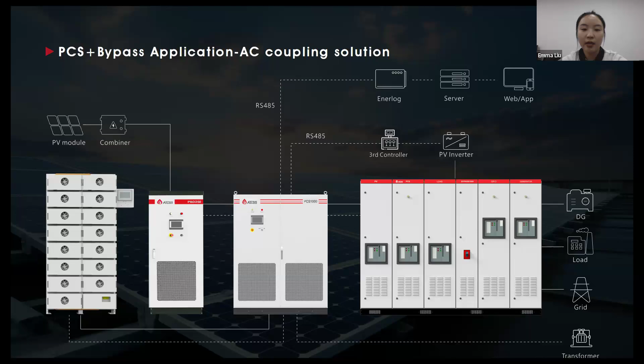Check out this typical AC coupling diagram of PCS plus bypass. That's the solution we have applied for the factory and farm. PCS can switch between on and off grid within 20 milliseconds, which makes the system uninterrupted. You can check the left side. The DC power sources such as PV power and battery power, PCS will convert all DC power sources to AC power and through bypass to supply the loads. This is a typical AC coupling system of bypass of PCS.